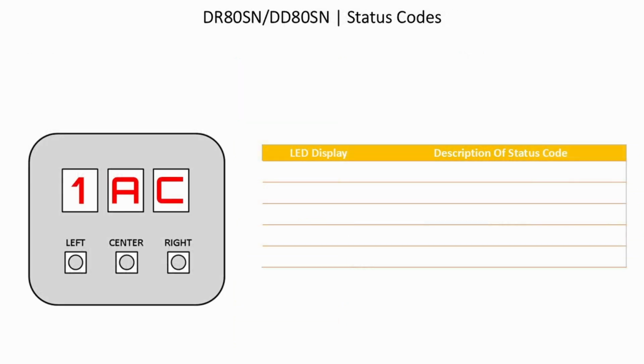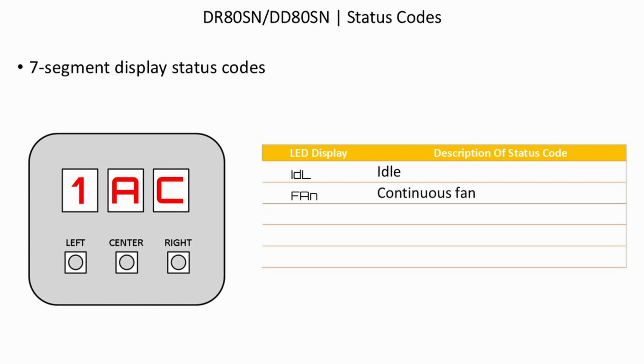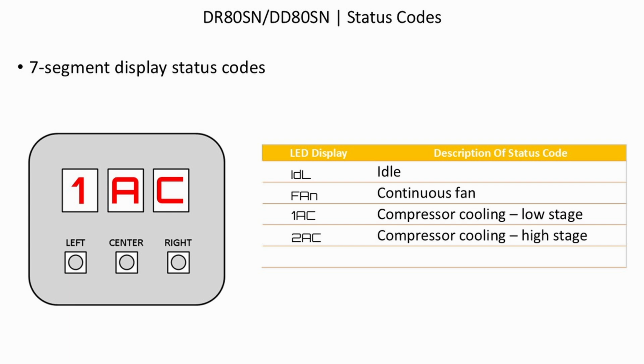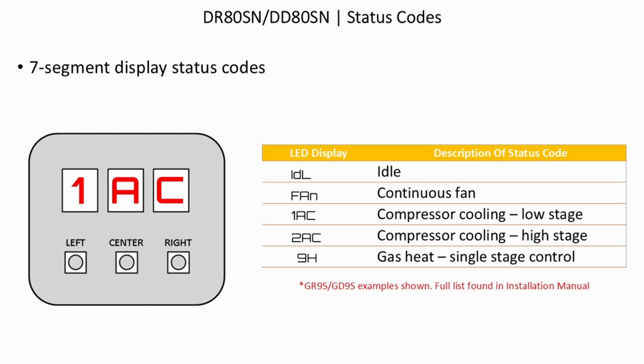DR80SN, DD80SN status codes. Here are the 7-segment display status codes. IDL, idle. FAN, continuous fan. 1 AC, compressor cooling, low stage. 2 AC, compressor cooling, high stage. GH, gas heat, single stage control. Note the G looks like a 9 on the display. GR9S and GD9S examples are shown. Full list can be found in the installation manual.